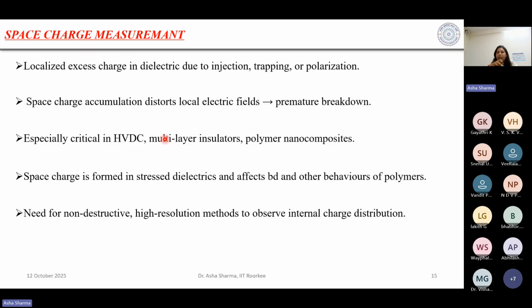Let's say I have the whole XLPE insulation in my underground cable, and at a certain point, due to any reason, I have some accumulation of charges, some positive charges, some negative charges. These produce their own electric field, right? There is one high voltage that we apply across these two electrodes. The electric field produced by these charges may oppose the electric field produced by the applied voltage, or it may add to this electric field. If the field produced by the space charge within my XLPE insulation in the underground cable is in opposition with the main electric field, then that's not an issue. But if it is in addition with the main field, it causes an issue.